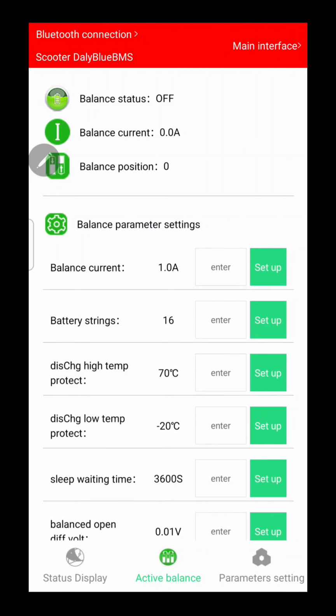So this is now just looking at the parameters for the active battery balancer within the BMS. What it's telling us is that it will use a 1 amp current to balance the battery cells, maximum of 1 amp. So if it has to discharge one of the high voltage strings to bring everything into balance, it will do that at a maximum of 1 amp. It's telling us we've got 16 battery strings.